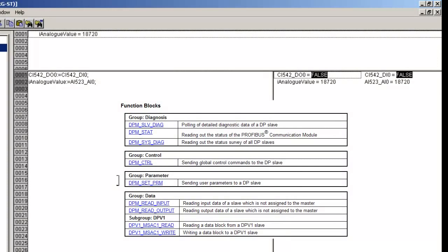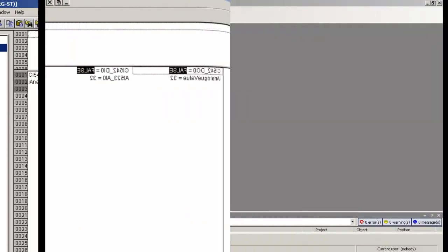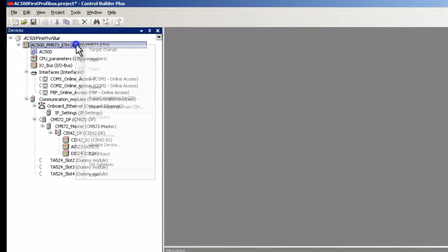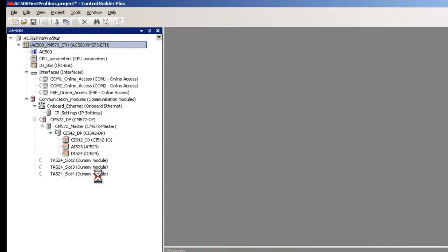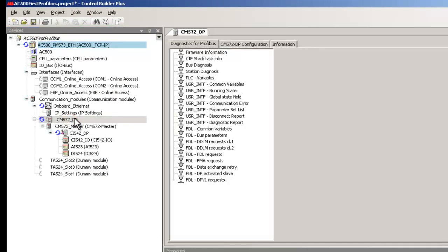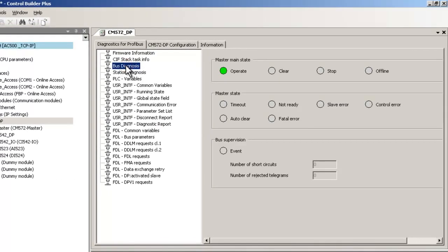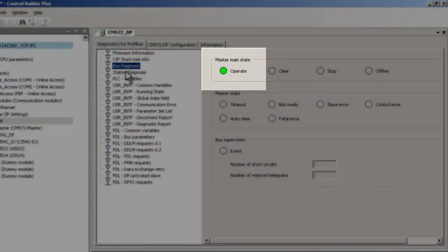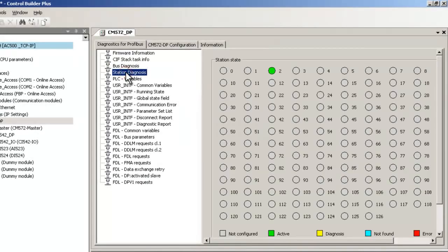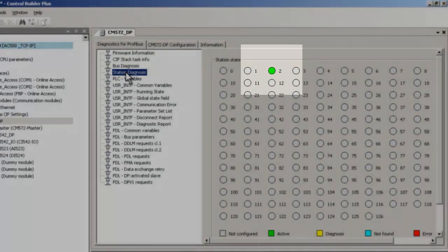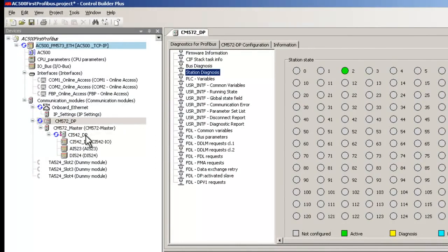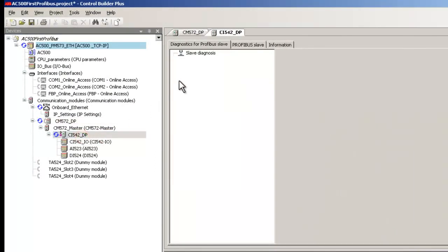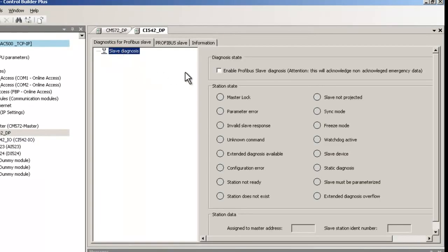Additional PROFIBUS diagnostics is provided when we establish a second connection to the PLC out of Control Builder Plus. By clicking on CM572DP branch, we get more diagnostic information. The option Bus Diagnosis shows the state of the master and bus supervision data. We can see the master is currently exchanging data with slave. Station Diagnosis option shows us an overview of all PROFIBUS slaves; currently slave number 2 is working properly. If you wish extended slave diagnostics, you could double-click on CI542DP in the tree and enable it.